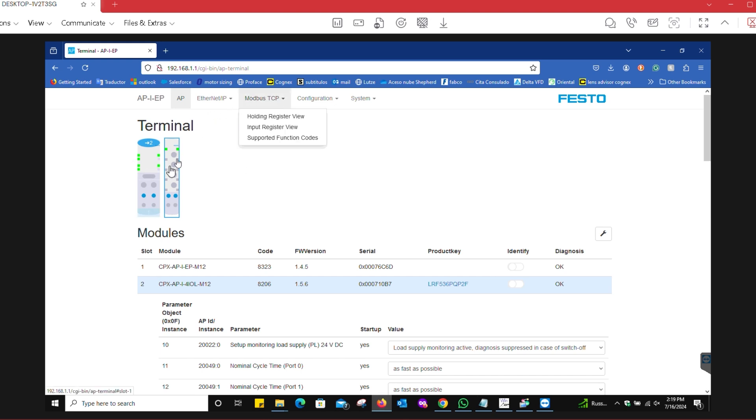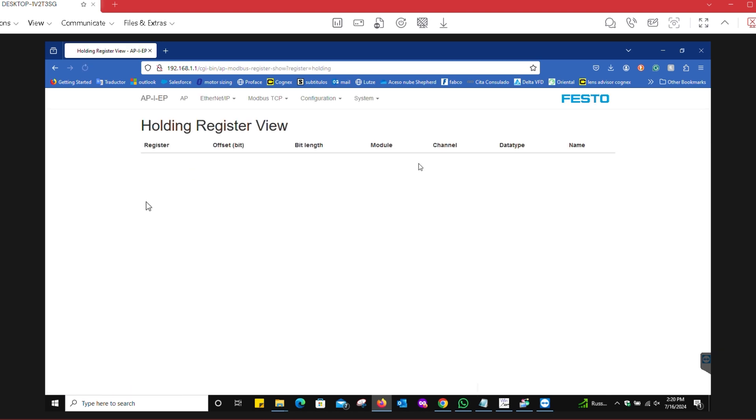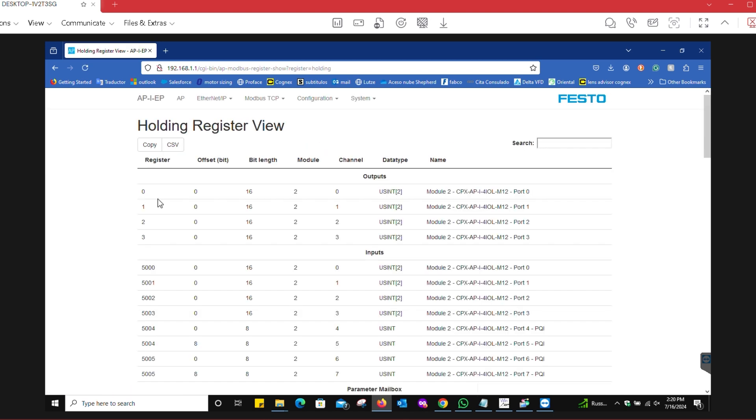On the holding register view, you're going to get all of the holding registers for outputs and inputs. The important part to notice is where the offsets are for the registers. The outputs start from zero, but the inputs start from 5000.